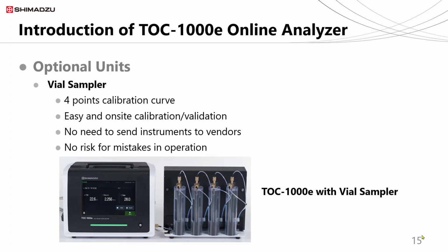Let's talk about the optional accessories for TOC-1000e. This unit is measuring online samples. Meanwhile, you need calibration or validation process time to time. If you need to perform these actions, you need to have the vial sampler option.